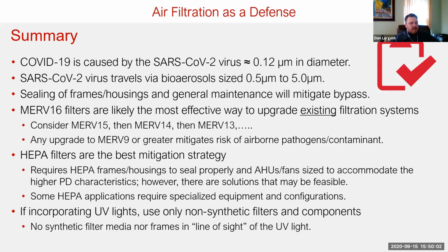And then if you are incorporating UV lights, we kind of touched on this earlier, but if you can incorporate them such that the filters are not in line of sight of the UV light, that's your best course of action. If that's not possible, then you need to use filters that do not use synthetic media or synthetic plastic frames and such. You need to go with glass media and metal frames.